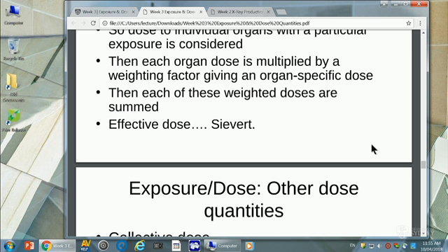I could do this by measuring the air kerma, and then I can convert that into a dose. Or if you're the patient here, I can put a device on you that measures the radiation. So we can directly measure it. And is that related to the kVp or mAs? Yes, for sure. If you give a higher kVp or higher mAs, you'll increase the dose.